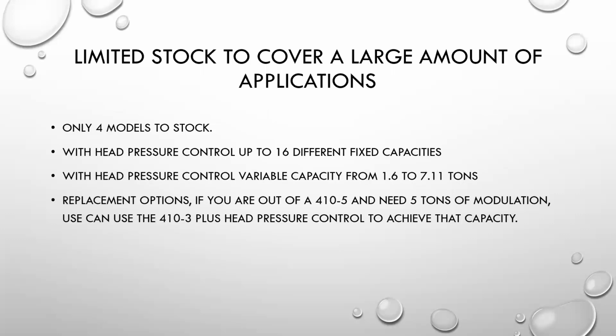Limited stock for those that will want to stock this. Only 4 models. And with head pressure control, you have 16 different fixed capacities. With head pressure control, variable capacity from 1.6 tons to 7.11 tons. That is the amount of modulation. That is not the size of the unit. Replacement options: if you were out of the 410-5 and needed 5 tons of modulation, you can use the 410-3 plus a head pressure control. All this is contained within the specification sheets, which you'll see an example of a little bit later.